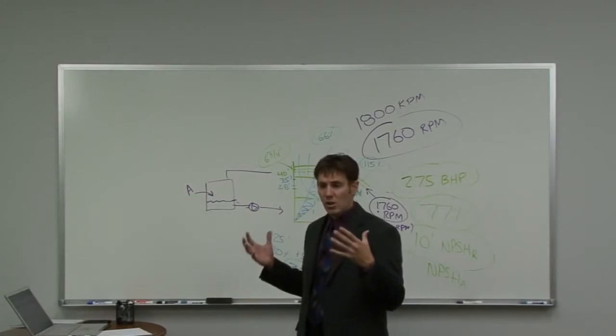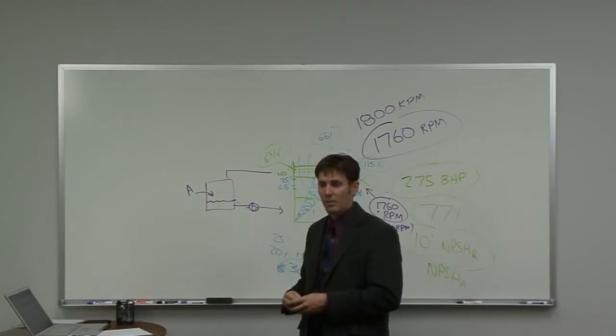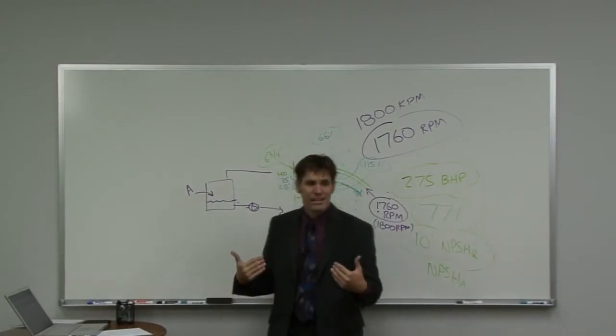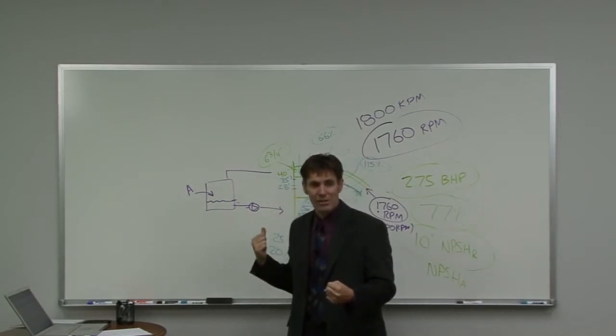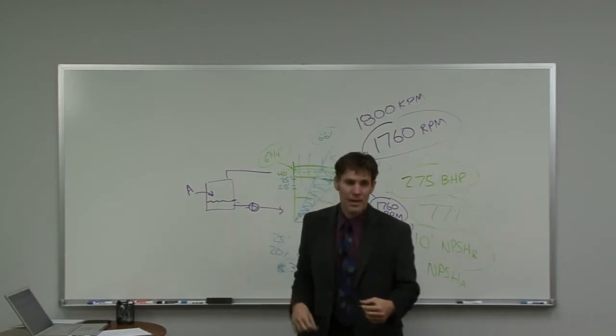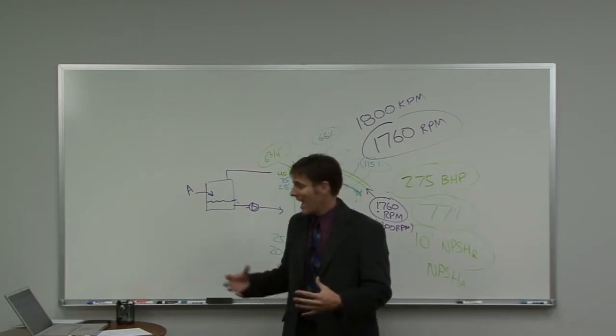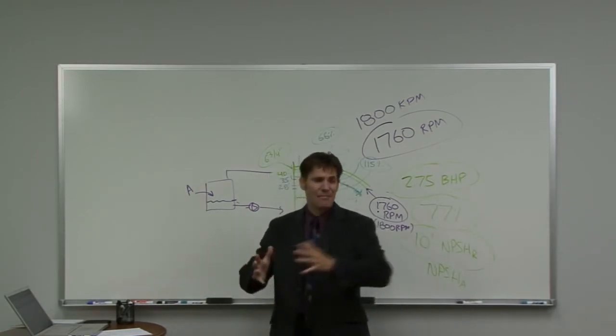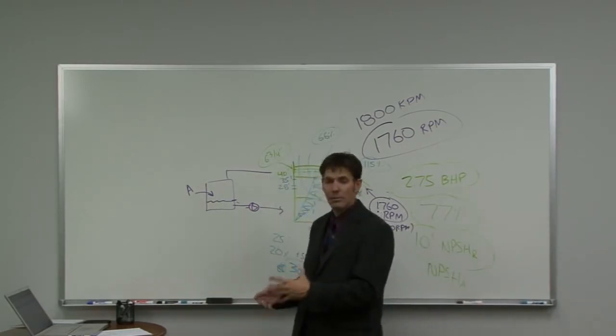Well, I'm looking over here at the motor sizes, and with the bigger pump I'm looking at 20 horsepower, the smaller pump I'm looking at 15 horsepower. What would I suggest? Again, we talk about this in another class, but I would suggest a flexible coupled or a split coupled pump, because I don't want to be that maintenance guy who's got to change that mechanical seal or trim the impeller or change the bearings and have to do that by taking that big 15 horsepower or 20 horsepower motor off.